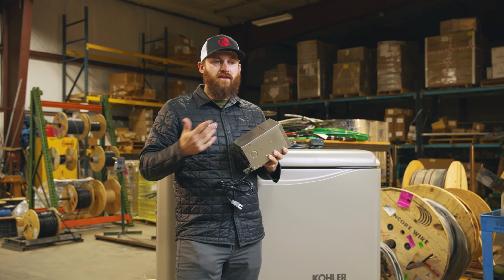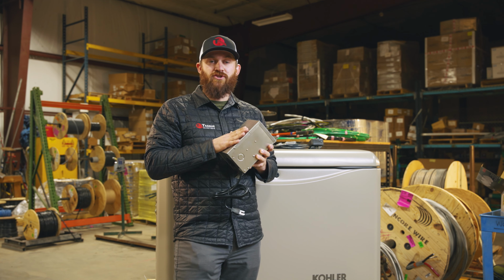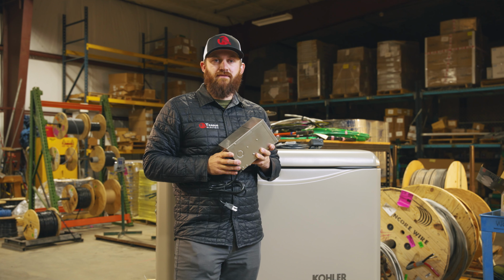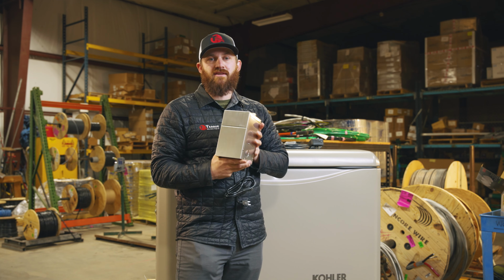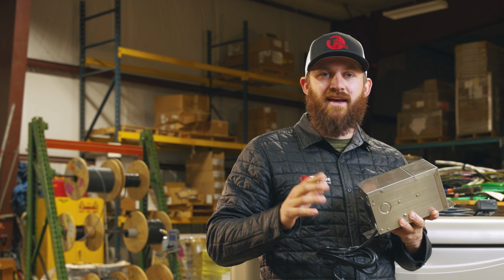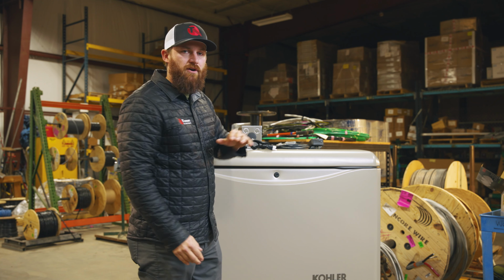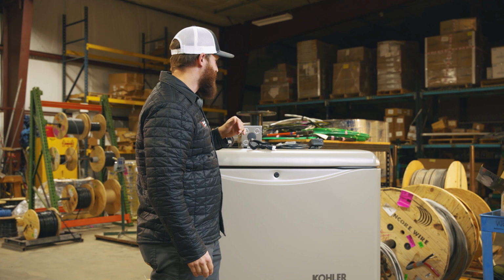Depending on how many lights you need or you want, or your layout, is going to determine how much capacity you need. So you need to know the wattage of each light and see if the transformer has the capacity for all those to work, because you don't want them dimming in and out. You want to make sure they all work properly. And so those are some items that are going to be involved when installing landscape lighting.